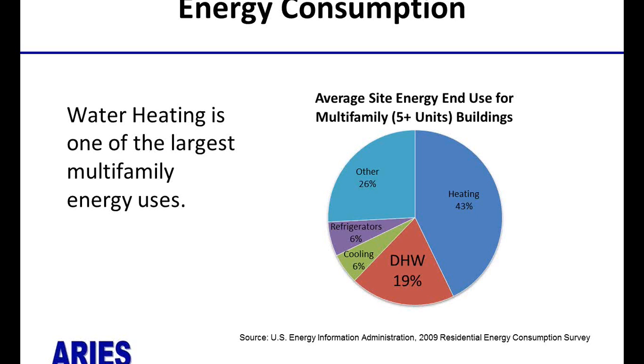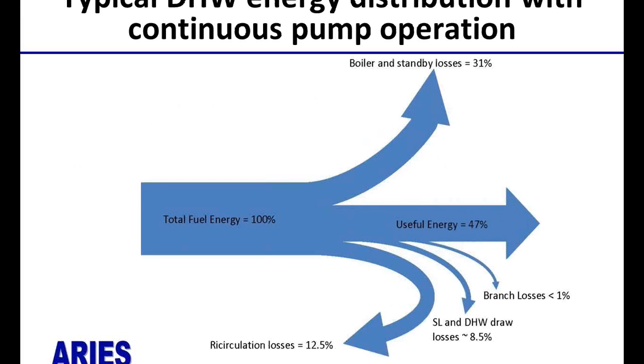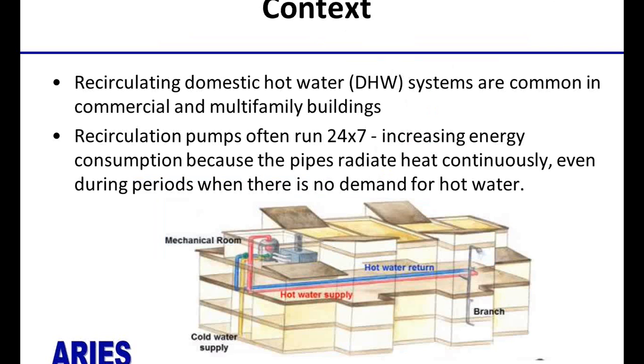So just some background, energy consumption for water heating in multifamily buildings is a significant share of site energy use, nearly 20% nationally, according to the Energy Information Administration. And energy efficiency of central water systems in multifamily buildings can be very wasteful. This diagram shows for one of our sites, and this is typical of other sites that we've looked at and others have studied, that perhaps only half of the energy that is generated at the water heater actually reaches the end user as useful energy. The rest is lost to either boiler losses, standby losses, recirculation losses, or other losses.